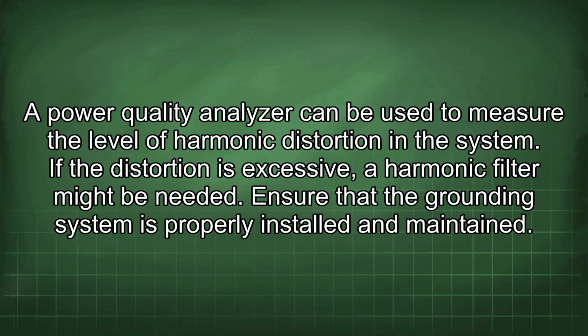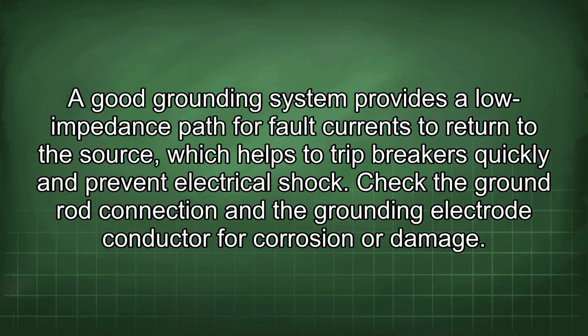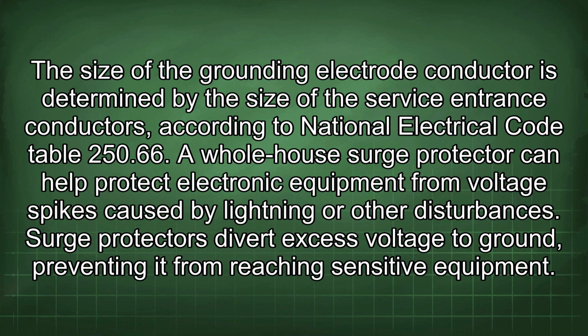Ensure that the grounding system is properly installed and maintained. A good grounding system provides a low impedance path for fault currents to return to the source, which helps to trip breakers quickly and prevent electrical shock. Check the ground rod connection and the grounding electrode conductor for corrosion or damage. The size of the grounding electrode conductor is determined by the size of the service entrance conductors according to National Electrical Code Table 250.66.